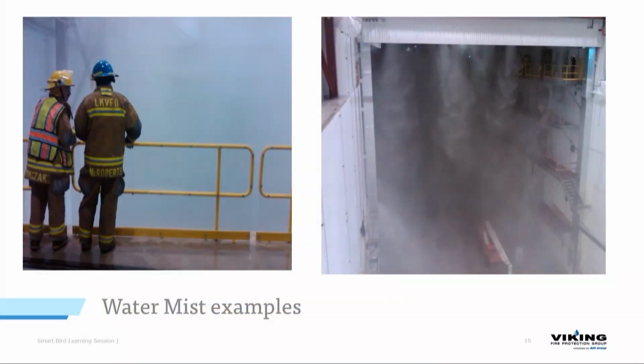Here's an undisclosed location somewhere in northern Minnesota. You can just see the high level of fog here. It is just impenetrable. You can see the nozzles just dropping fog down. There's multiple layers that come off of this one. This is based off of a very large fine water mist fire pump that was specifically built custom for this project. Again, lack of water, even lack of heat. You really don't need more than a 55-gallon drum of water and some electricity to get one of these systems up and running for a facility.